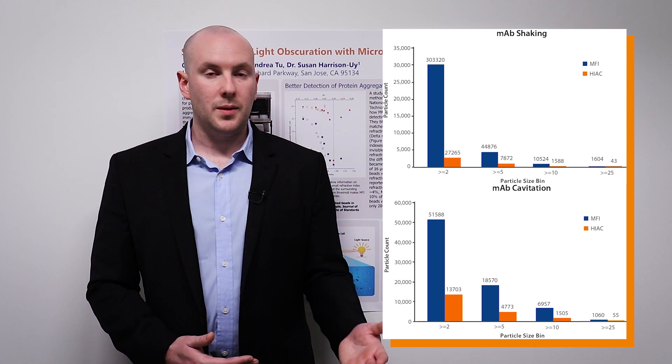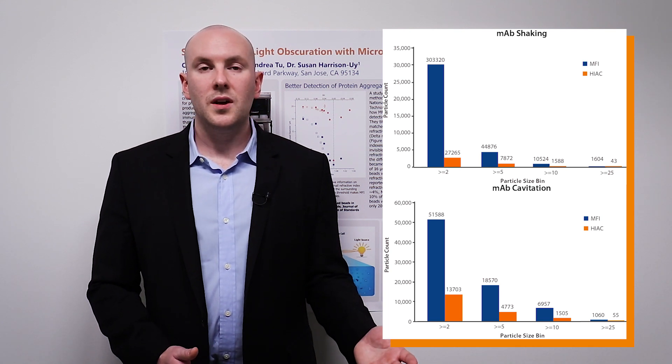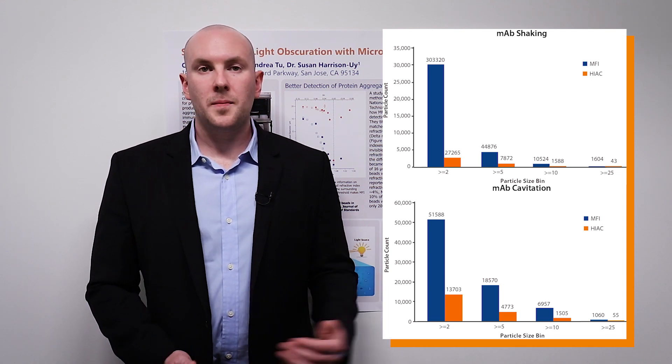In fact, MFI measures up to 10 times more particles for some of the size bins. Because of its enhanced ability to detect protein aggregates, MFI is commonly employed as a formulation development tool, a process development tool, and is heavily involved in final product QC.